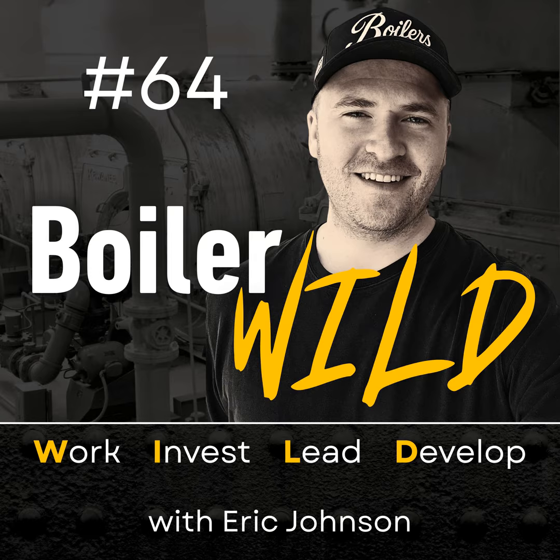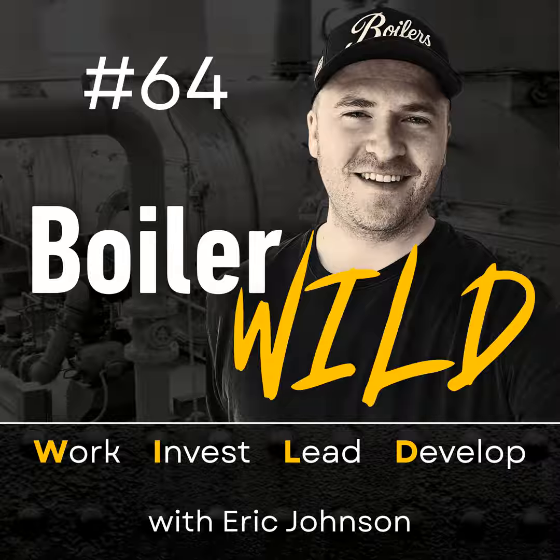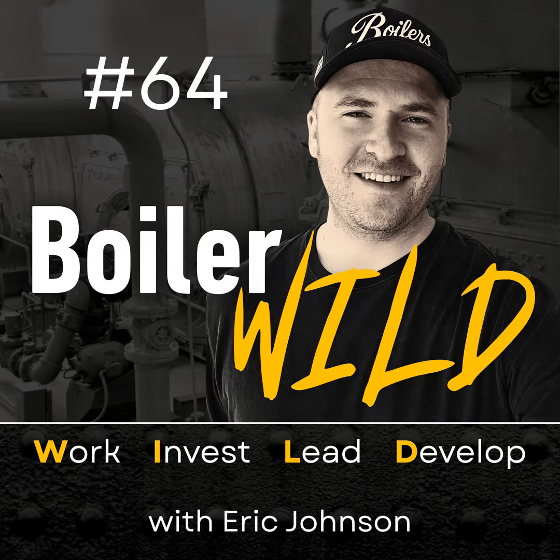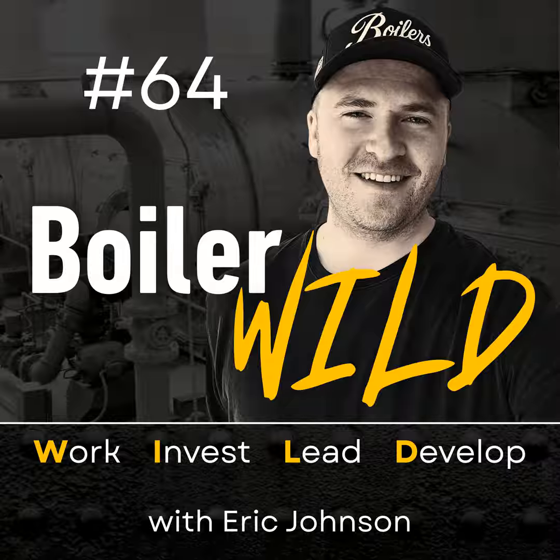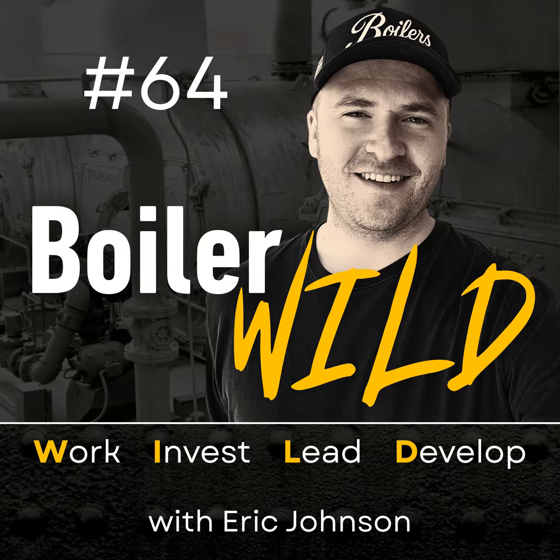Also, another note that you need to be mindful of is when you walk into the boiler room and the boiler's not running and you've already determined that you're in a safe environment and you've looked over the boiler and it seems like it's ready to go and everything's normal and the customer hasn't done any modifications or repairs, you're not coming back from anything abnormal, it just stopped running. Don't go around and push all the resets. So if you have a series circuit and you have 4 limits in that circuit and you just push all the resets on the limits that you know have resets, and then the boiler starts, you don't know exactly what limit tripped if the boiler doesn't start right after you push a reset.